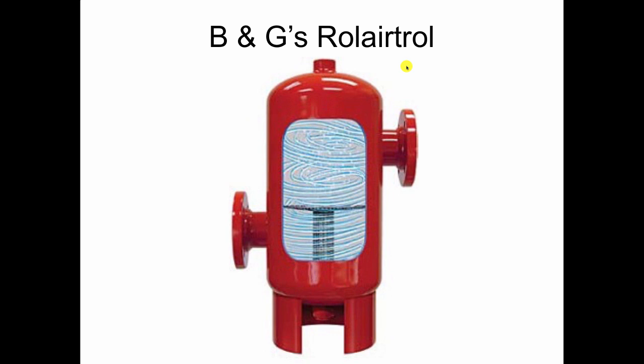Bell and Gossett years ago came up with what they call the Rolairtrol, which has a tangential opening on the side — in and out — so when the water comes in it spins in a whirlpool. They have a baffle in the center so the water has to squeeze by the edge of the baffle to go through the strainer and get out. In doing so, it has the least amount of air in it, because spinning like a vortex makes the lighter air go to the middle and the heavier water, which has less air, go to the outside. So these are all common air separators that you'll see out in the field.